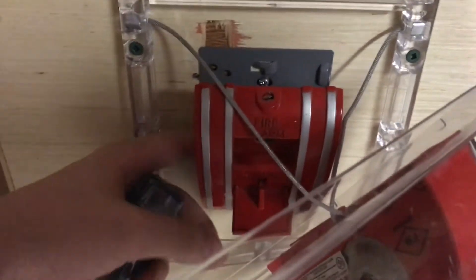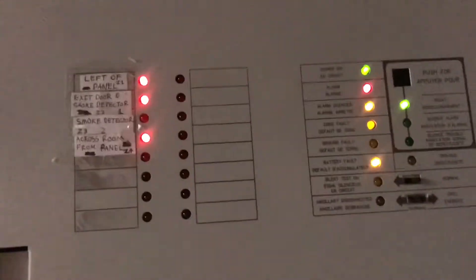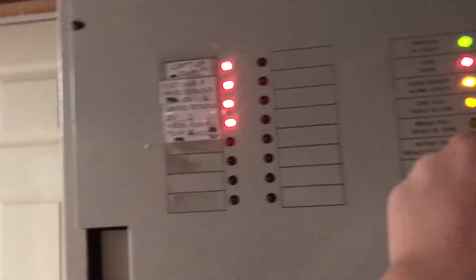Now we can go ahead and reset this one. I'm going to pull all the pull stations on this last system test. It's pretty quiet. Might as well activate that smoke detector, and then we'll move over to the 6602. So all the zones have been activated, and this will be my final reset I'll do with this thing. This is the last time you're going to see this plugged in on the system — I'm going to power it down and plug in the 6602. Bear with me.